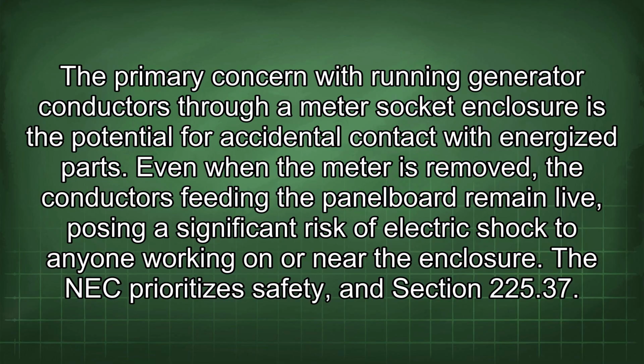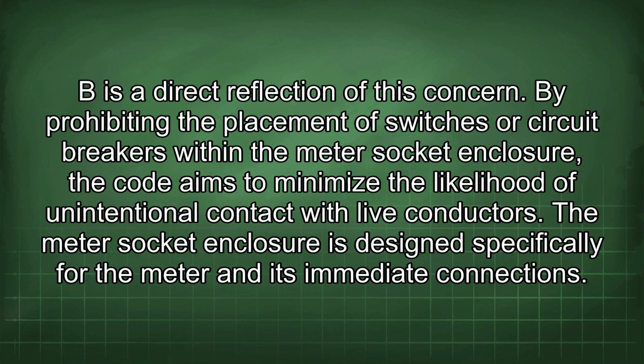The NEC prioritizes safety, and Section 225.37(B) is a direct reflection of this concern. By prohibiting the placement of switches or circuit breakers within the meter socket enclosure, the code aims to minimize the likelihood of unintentional contact with live conductors.